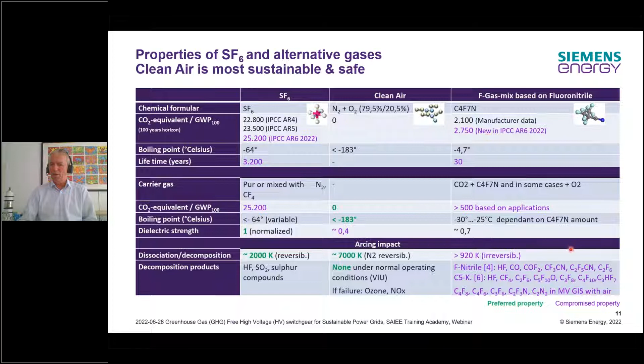So from our perspective, all the alternatives have good and bad things, and compromises have to be made. We decided that the clean air installation has the highest benefits also in operation, and we listed the benefits, which are even better than SF6 today, and also better than the different alternatives. So the global warming potential is 0, and the ozone depletion potential is 0. It's completely non-toxic regarding different aspects, also regarding carcinogenicity, mutagenicity, reprotoxicity. So it's a perfect gas toxicity-wise. It's non-flammable, highly stable, has a very low boiling point and no liquefaction.